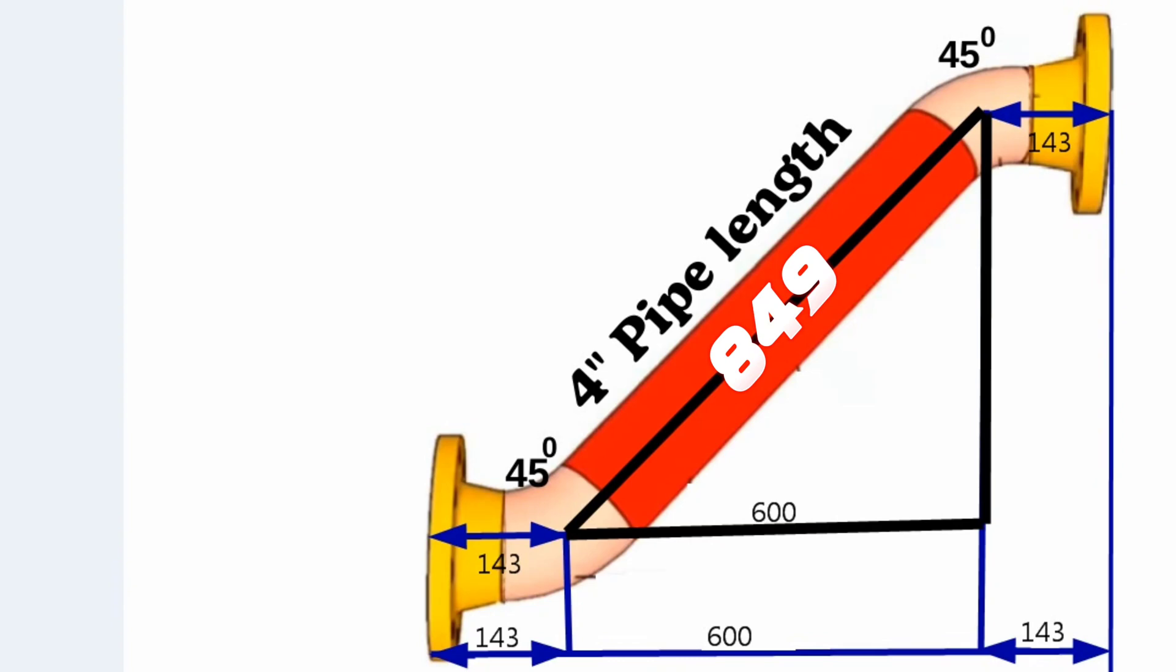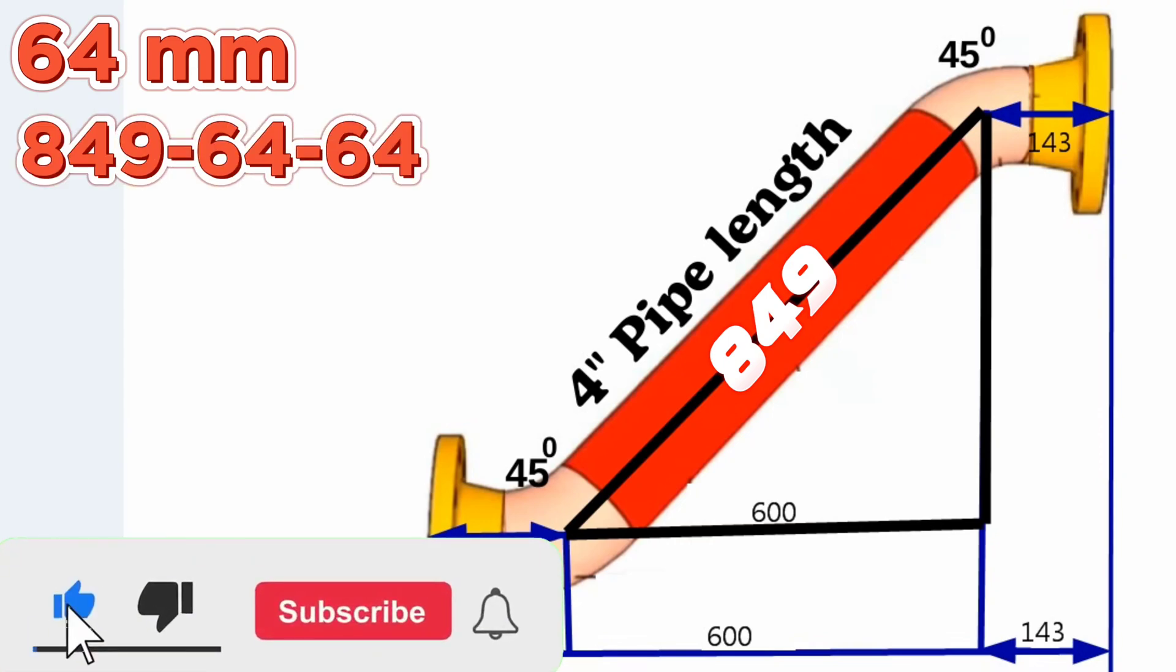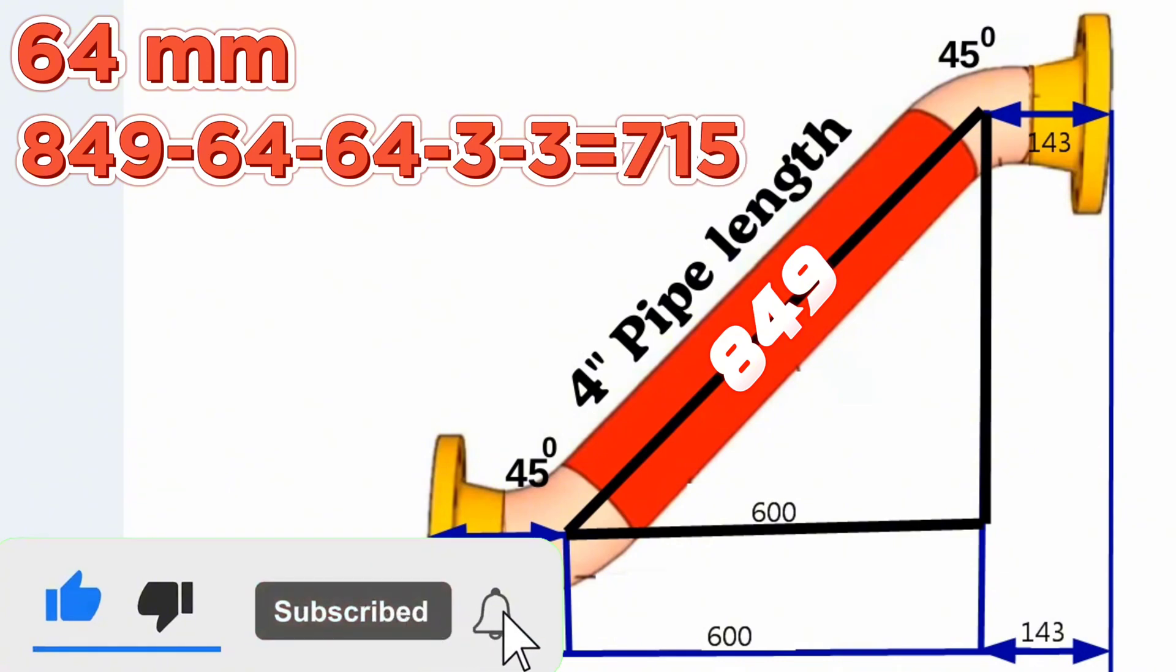We know the center to end of the 45-degree 4-inch butt weld elbow is 64 millimeters. Then 849 minus 64 minus 64 minus 3 minus 3 equals 715 millimeters.